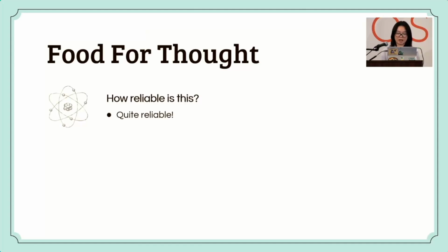Now, with any research, though, there's always lots of factors to consider and think about. Now, starting off, how reliable is this study? So my program published this experimental method last year in JECT, establishing a standardized protocol to measure platelet activation. But to ensure its accuracy, we compared our results within each trial run that we had, and what we found was that there was actually a minimum intervariation between each circuit run and at each time point where we measured the platelet activation. So it actually did ensure that this was a very reliable protocol that can be referenced in the future for comparative studies, and that's why we used it for this round of experiments.